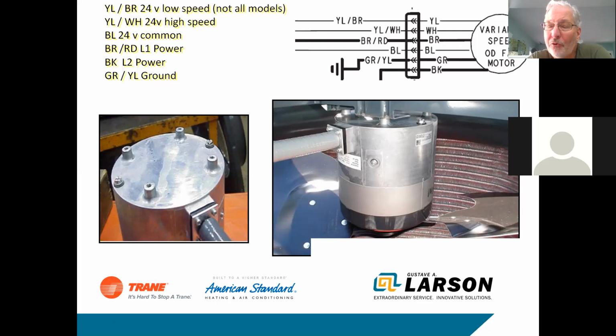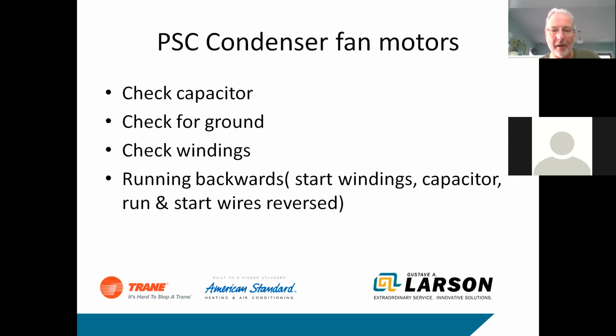Okay, so if you want to troubleshoot these, if you've got 24 volts to the motor and you've got 230 volts or 208 volts to the motor, and the motor's not running, it's probably a bad motor. It's pretty simple to troubleshoot. If you don't have the 24 volts to the motor, it's probably something in the low voltage circuit. If you look at the wiring schematics on these units with the ECM motors, that voltage comes right off the low voltage contactor. So when you energize the contactor to bring the compressor on, that should energize this motor, and that motor should run. If you don't have 24 volts there, then it's something in the wiring or in the contactor, elsewhere down the line. That's the real simple troubleshooting: if voltage is there, it should run. If it's not there, it won't run. If you have questions on any of this, give us a call. This is in the schematics with the units. Now, the more common thing that we see out there are PSC motors.